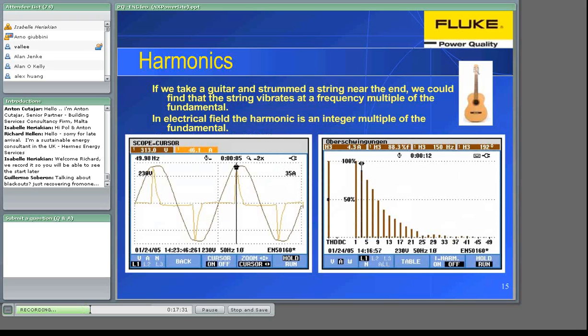In the electrical field, a harmonic content generates a distortion of the sine wave. The current shape is different than the voltage shape. We are faced with a load that draws current in a non-sinusoidal fashion. The picture on your left shows a flat-topping voltage originated by a very distorted current over the supply impedance. Harmonic distortion caused by nonlinear loads results in current higher than expected owing to the content in harmonic frequency components.